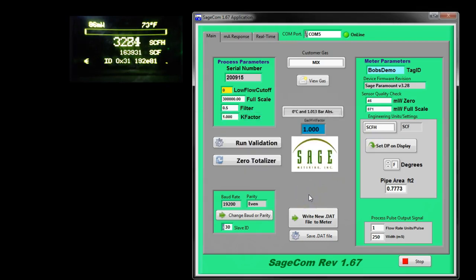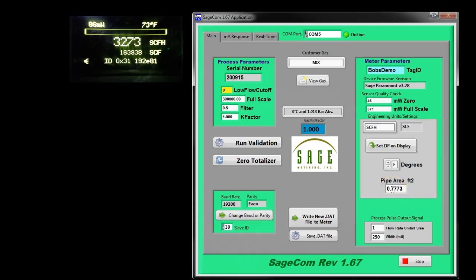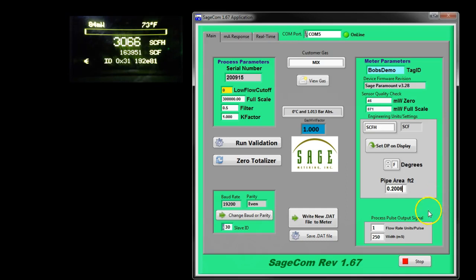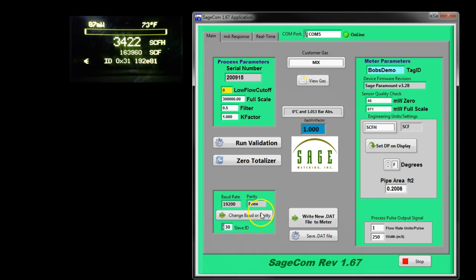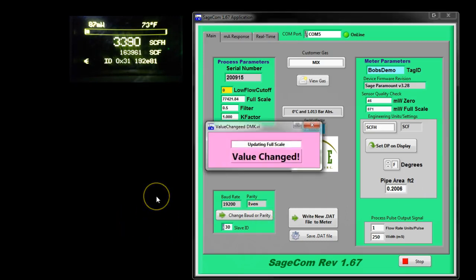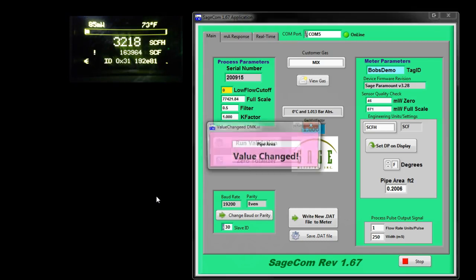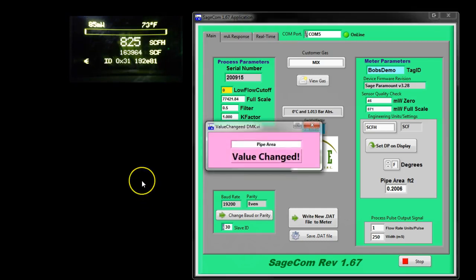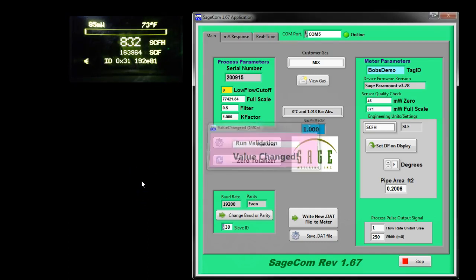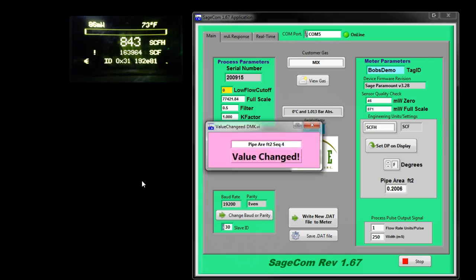Perhaps you want to change the pipe area and it is recommended to use this field for pipes 4 inch and up. Well, I'm going to change it to 0.2, which would be a smaller pipe by a couple of inches because we're going from 12 to 6, so let's put in 0.2006 which is a 6 inch schedule 40 pipe and you'll notice when I press the return key, notice what happens to the SCFH. It's going to change on the display because the pipe area is much smaller and the flow rate is going to be smaller.